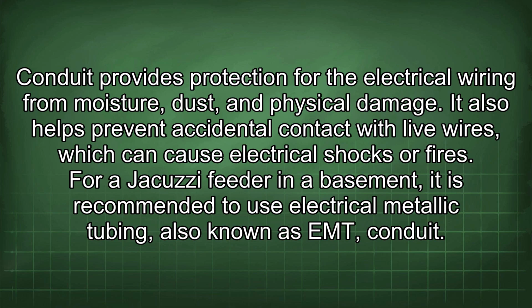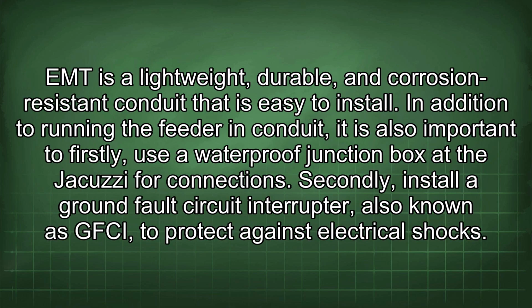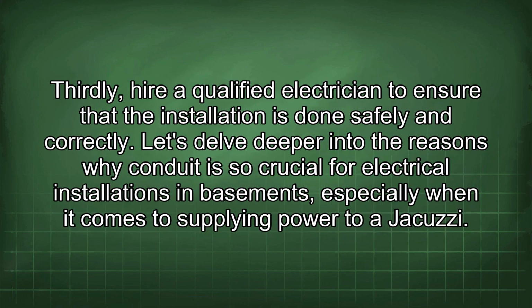For a jacuzzi feeder in a basement, it is recommended to use electrical metallic tubing, also known as EMT, conduit. EMT is a lightweight, durable, and corrosion-resistant conduit that is easy to install. In addition to running the feeder in conduit, it is also important to, firstly, use a waterproof junction box at the jacuzzi for connections. Secondly, install a ground fault circuit interrupter, also known as GFCI, to protect against electrical shocks. Thirdly, hire a qualified electrician to ensure that the installation is done safely and correctly.